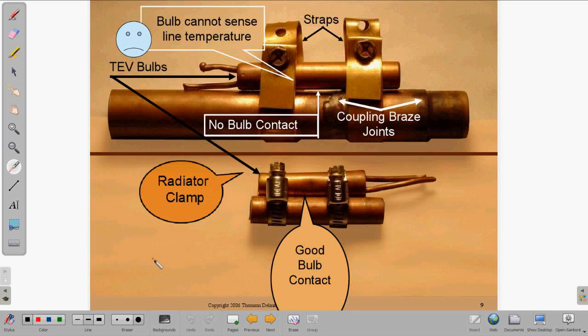Here's something that can happen if you're not paying attention, and something to look at if you're troubleshooting a TXV problem: an improperly mounted sensing bulb. It's very easy, if you have a braze joint here or coupling, to mount that sensing bulb and not have it securely fastened and touching the evaporator coil. So you just need to make sure that you have great bulb contact here, because it's got to sense that temperature so that that TXV will react properly.